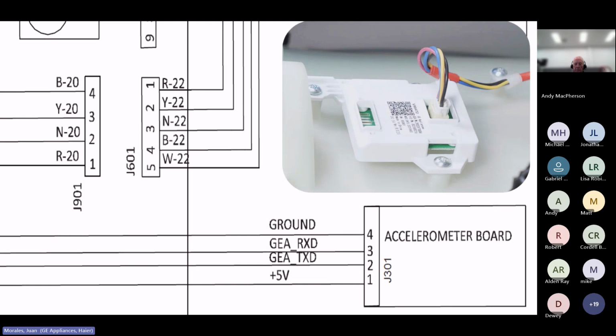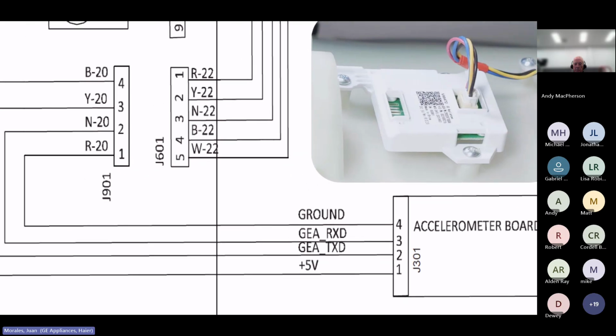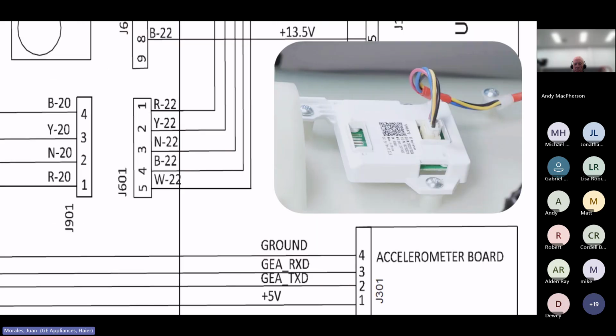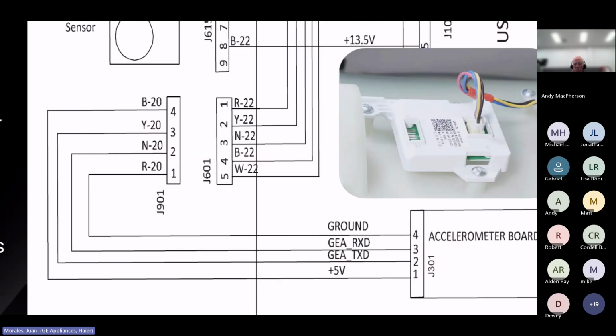If there's no voltage, you're going to have a fault code related to the accelerometer, but it's not actually your accelerometer, it's your main that's causing that. If you do have voltage and you get a fault code related to the accelerometer, then more than likely you have to replace the accelerometer. That's why it's important to know these symbols and signals.